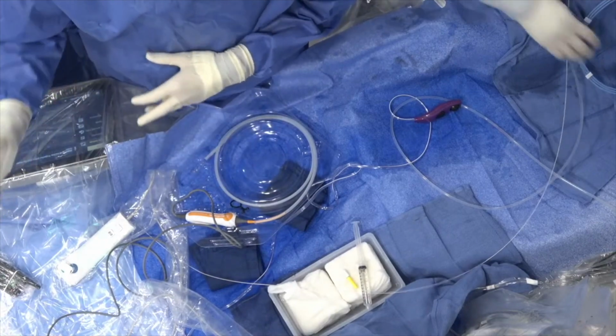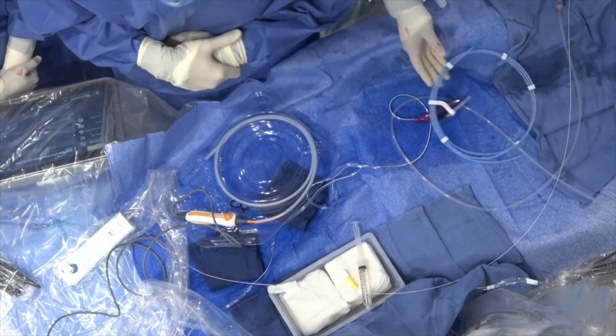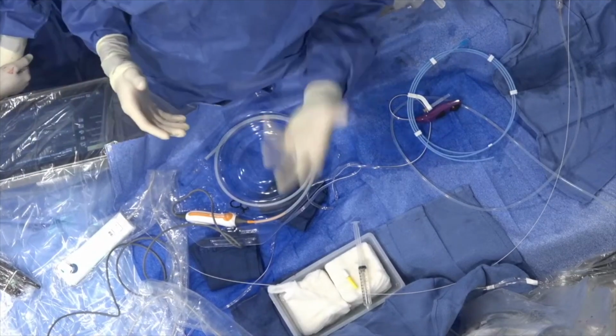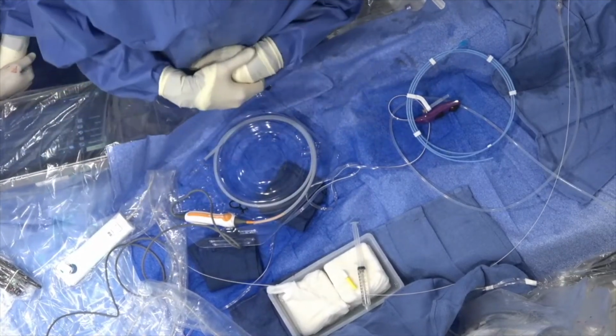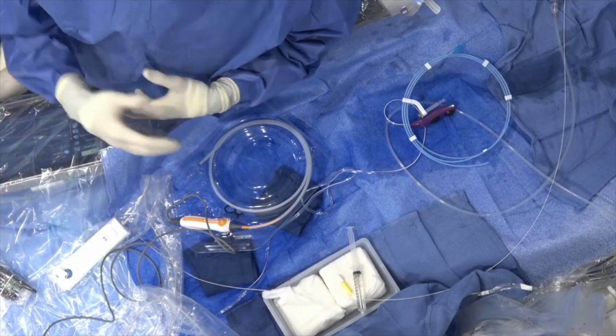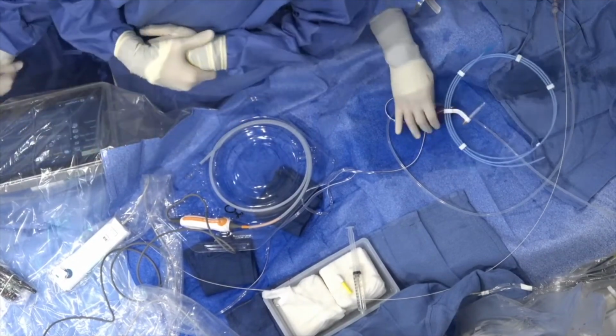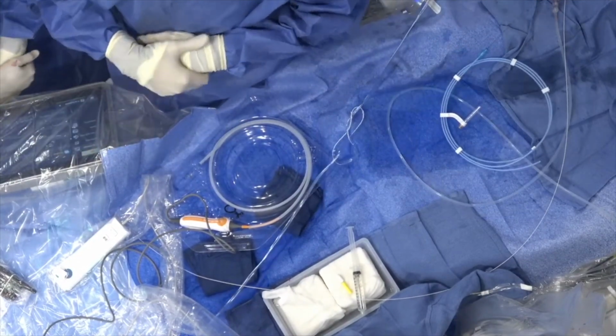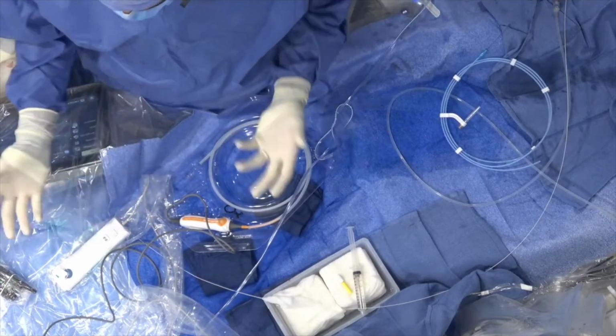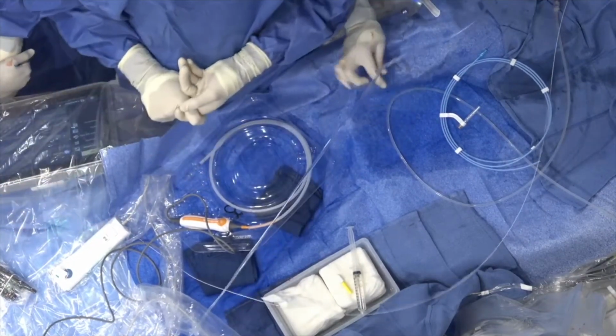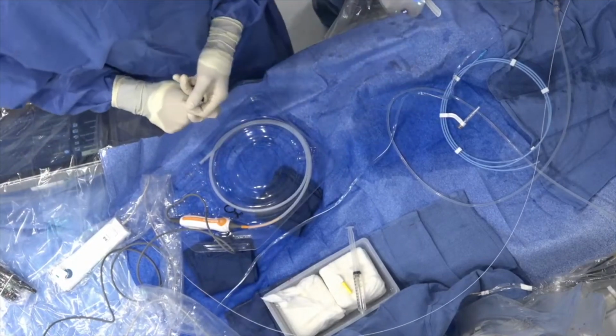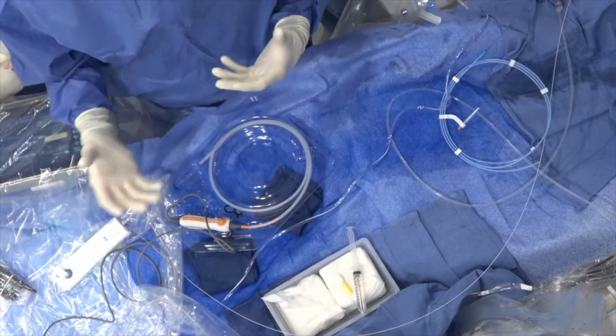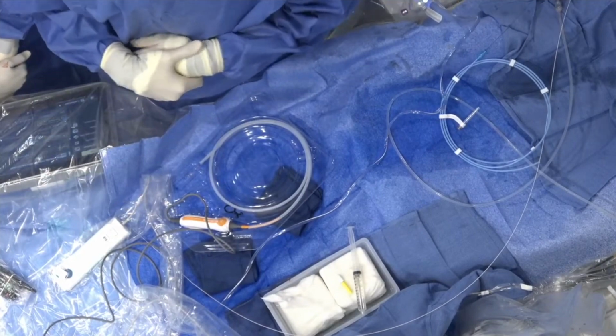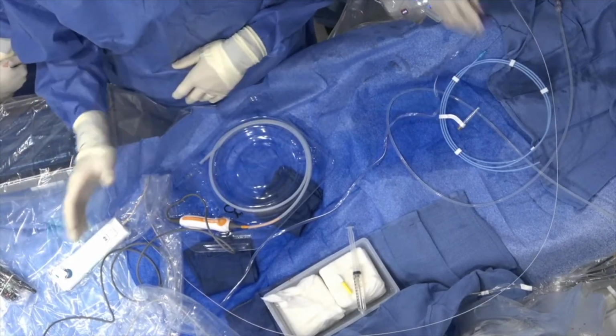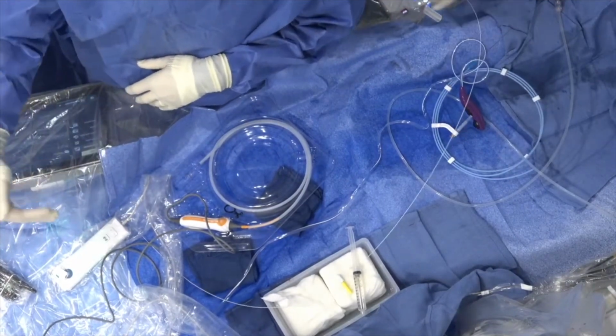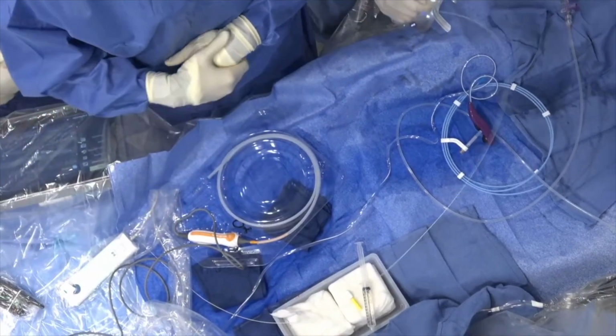The machine itself, again, does the bulk of the work. Assuming you have good contact, and again, we'll be able to talk a whole lot more about that, you should be able to deliver the total of the 60 seconds of the therapy. Sometimes what may happen is that you may have issues where you have inappropriate vessel contact, too much impedance, and so on and so forth. And when this happens, the machine will make it very, very clear to you, and it'll turn that catheter off. It'll turn either just that specific electrode off, and I'm sure we're going to run into that here.